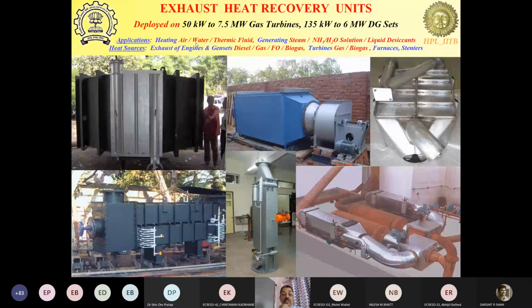Water can be heated in a pressurized state above 100 degrees centigrade also. We have heated thermic fluid right up to 250 degrees centigrade also. And we have generated steam up to 16 bars. And ammonia water solution can be regenerated, or liquid desiccant streams can be regenerated using the waste heat from gensets and all those things.